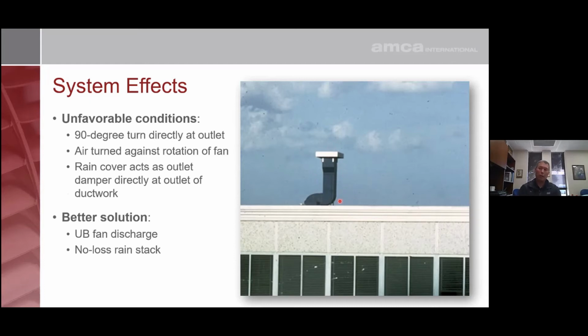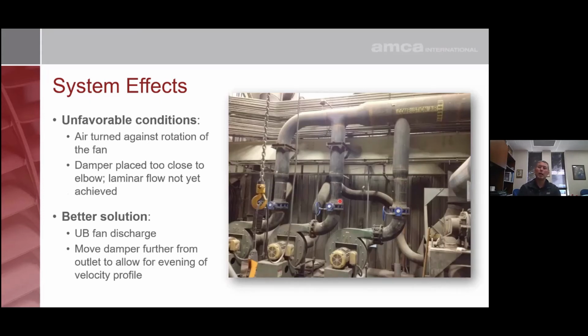Here we have an industrial application, another position C elbow. Fans are top horizontal fans, blowing into this elbow, has to get re-accelerated back out and into the overhead plenum that's gathering air from each one of these three fans. I see a lot of position C elbows in the field, and that's how come it's so easy to get pictures of them. And I think a lot of it is because people just don't realize how much mass a fan moves. If you're moving 26,000 CFM through a fan, which is a medium-sized fan, you're moving actually 1 ton of air through that fan every single minute.